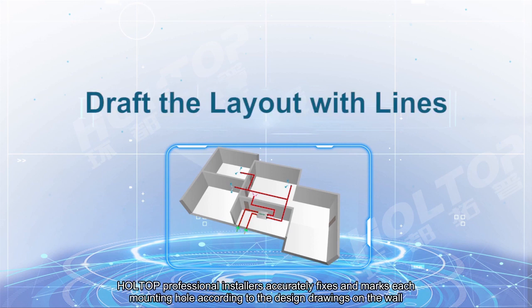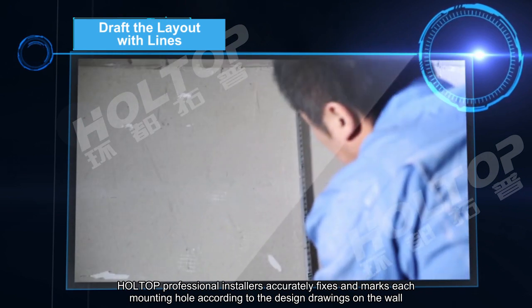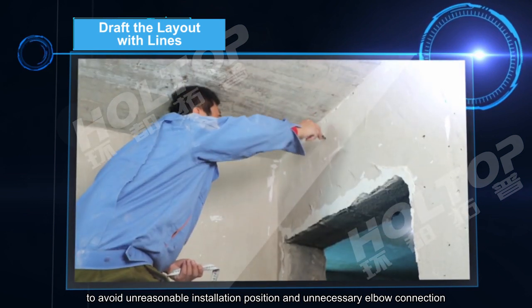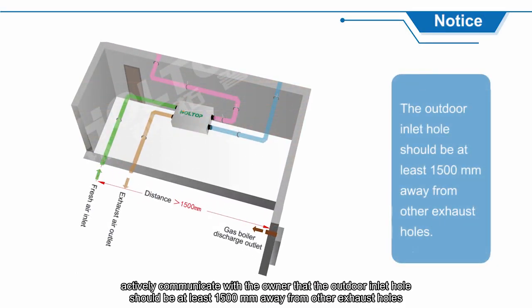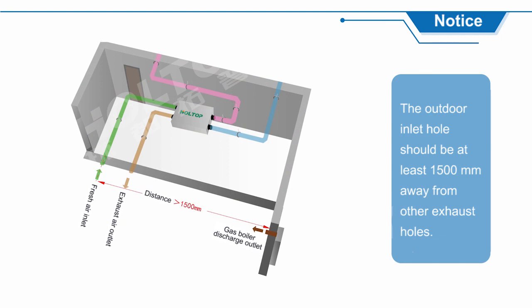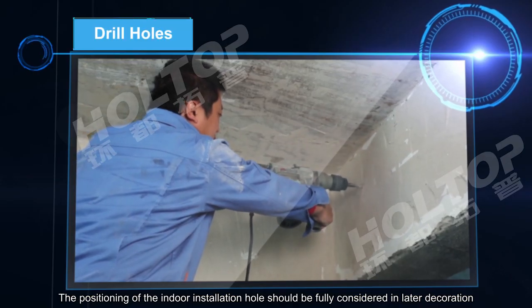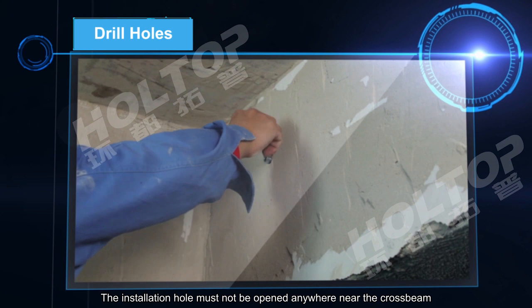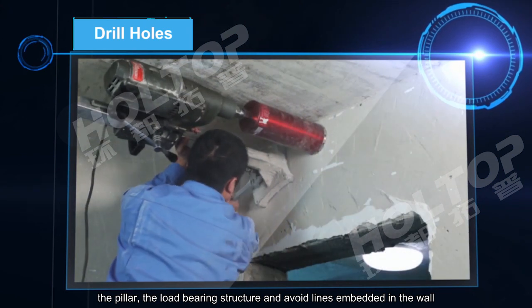On the construction site, HOLTOP professional installers accurately fix and mark each mounting hole according to the design drawings on the wall, to avoid unreasonable installation positions and unnecessary elbow connections. They also actively communicate with the owner that the outdoor inlet hole should be at least 1500 mm away from other exhaust holes, and that the positioning of the indoor installation hole should fully consider later decoration.